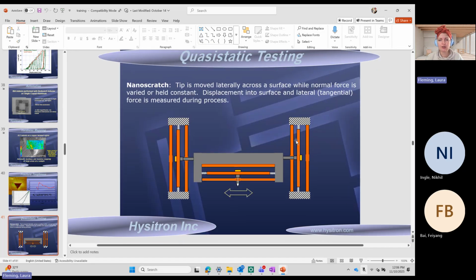Similarly, in order to scratch, what we did is we took two of the transducers and turned them on their sides. So that now we can also move in this lateral direction, right? These center plates can move back and forth like this. One of them is essentially a dummy. It's there because we needed something that would move, would push against. And the other transducer is calibrated. So just like the normal force transducer, we have also calibrated this one to have accurate force and displacement data.